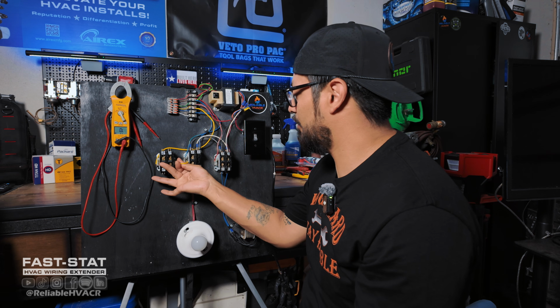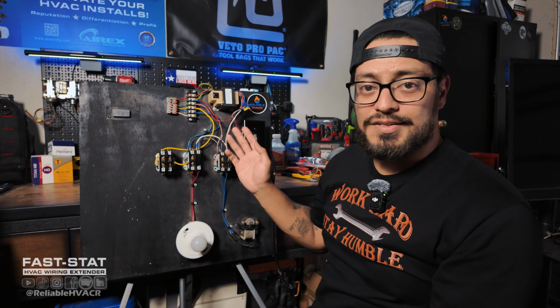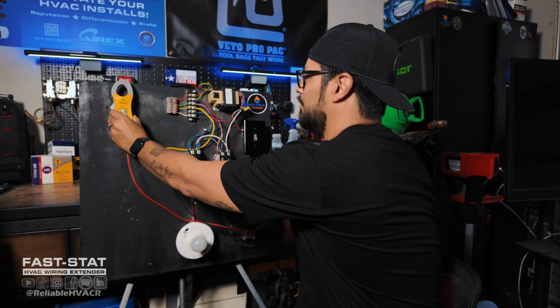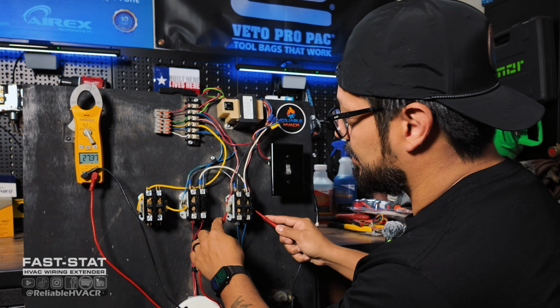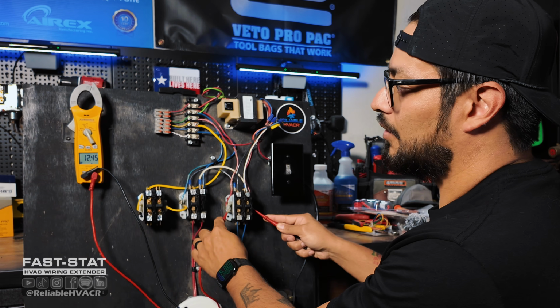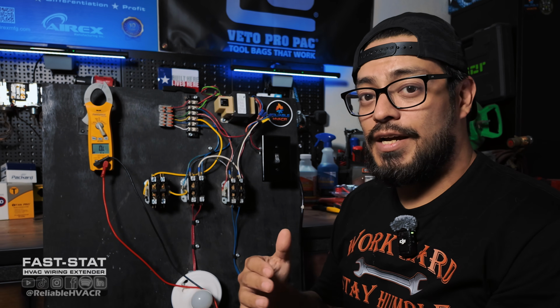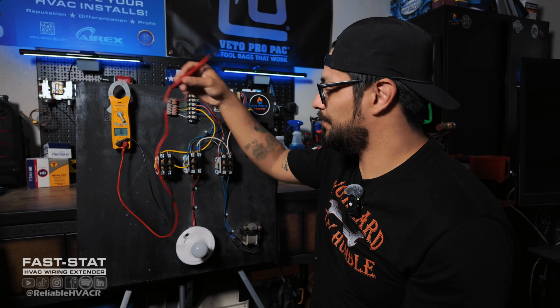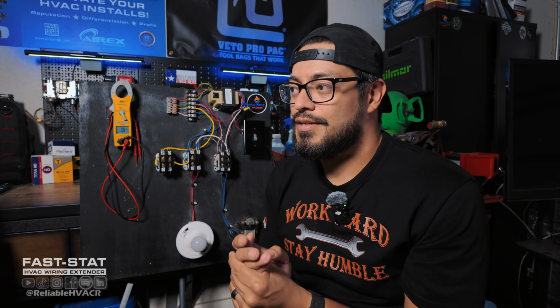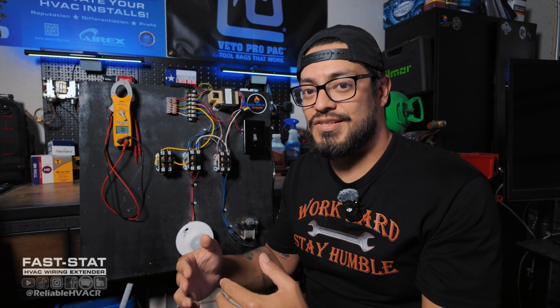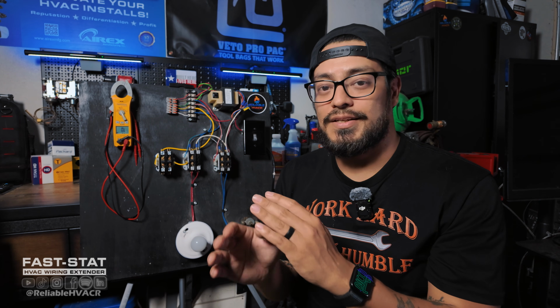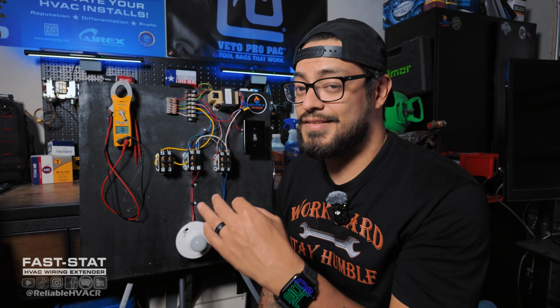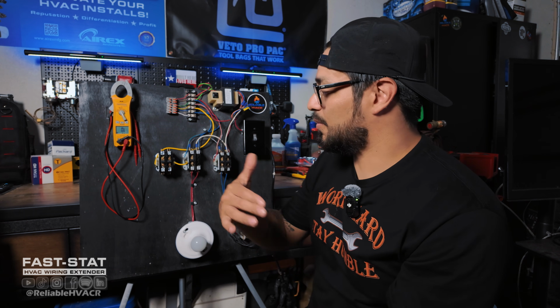A contactor, I've done this one before. If you're checking a wire that is still hooked up to the contactor, it's going to give you a reading. If we go to resistance, that one is going to give me 12 ohms of resistance. So you can have 12, 15, there's different numbers for contactors. So you need to have something of resistance. If you have like 0, 0.01, 0.02, there's no resistance. That means it's shorted. So if you guys are checking by resistance, you need to have some sort of resistance or overload, OL, and that way it's telling you that there's nothing touching. If there is little to no resistance, that is a short, which brings me to my next one.